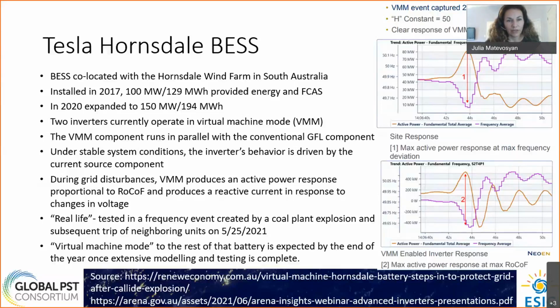Currently 2 inverters there are operated in virtual machine mode and so being tested. The virtual machine mode component runs in parallel with the conventional grid following component, so it can switch mode between grid forming and grid following effectively. Under stable system conditions, the inverter will behave like a grid following inverter, and during grid disturbance, it will produce active power response proportional to rate of change of frequency and inject reactive current in response to changes in voltage.